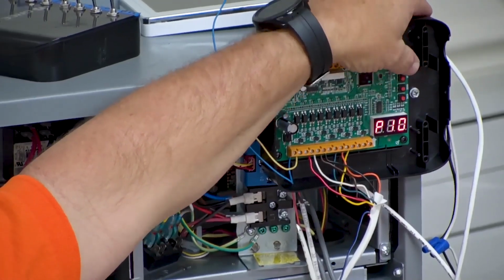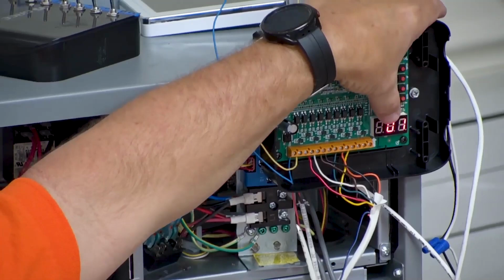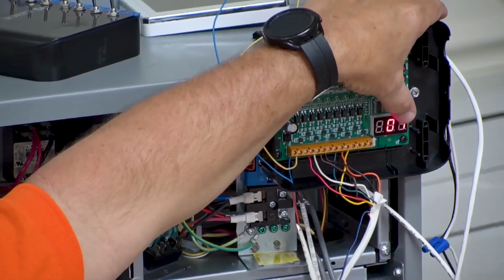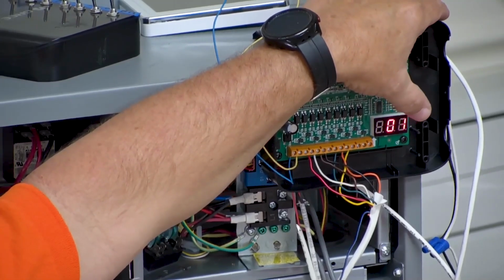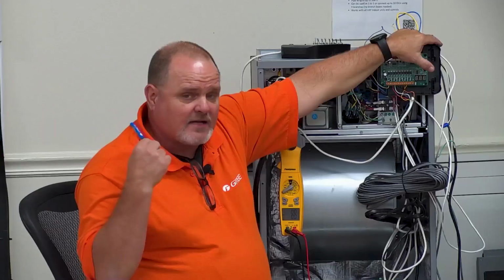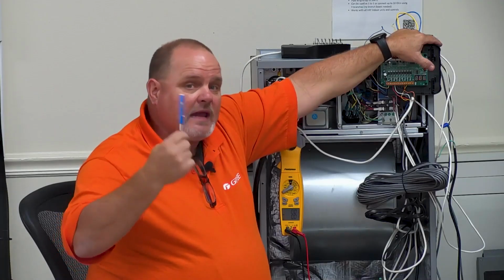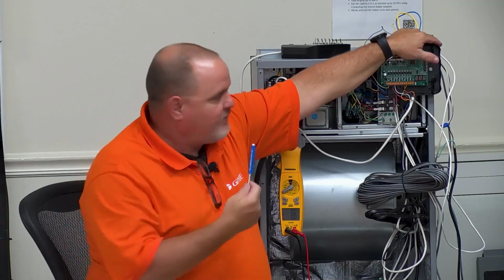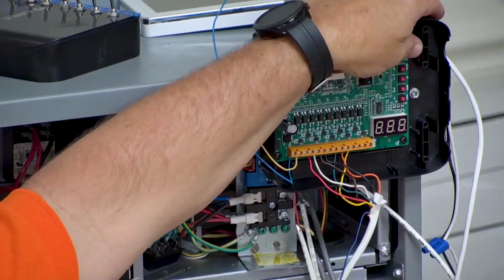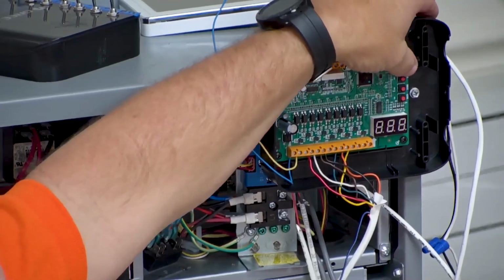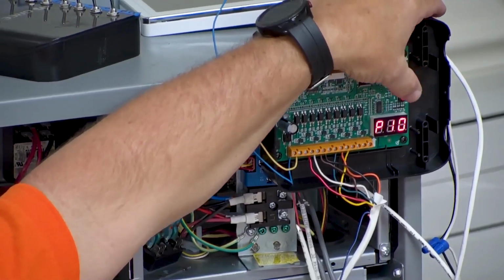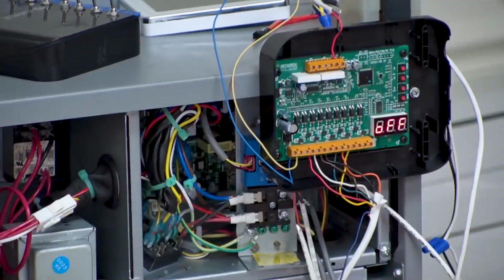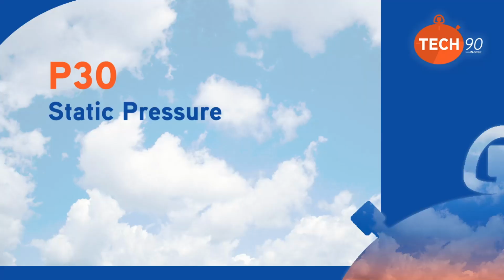You would set P10 to 01 if you want it to be the master, 00 if you don't want it to change. So if one of the other units is the master and you want it to remain as the master, you leave that P10 setting at 00. Again, you hit enter to save it after you get it, and then the back button takes you back to the main screen. So none of this is hard to set. Let's see, what else do we got?